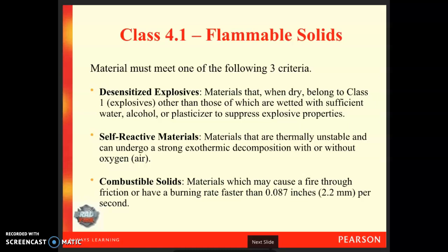The second group here are the self-reactive materials. These are things that are thermally unstable, and when they react, they can undergo a really strong thermal decomposition. And this can be done in the presence of air or even without oxygen. And then finally, we have the combustible solids. By definition, a combustible solid is a material that can cause a fire through friction or have a burning rate faster than 0.087 inches per second.